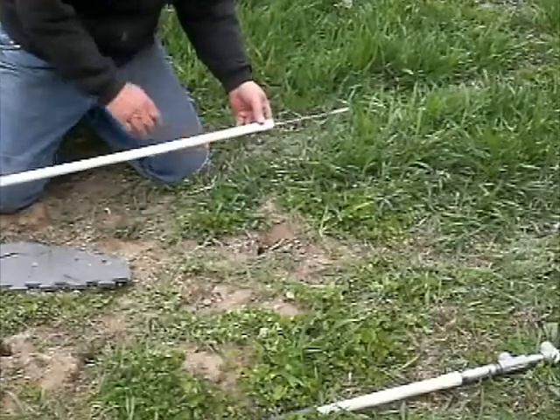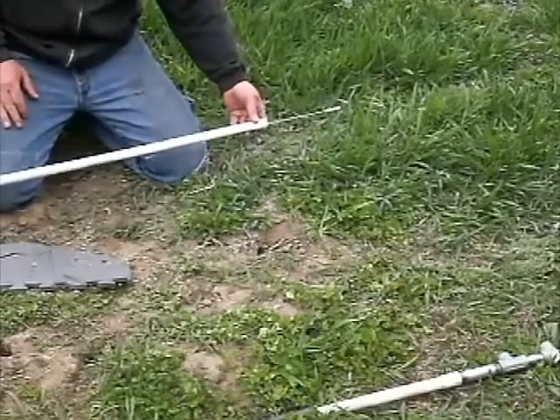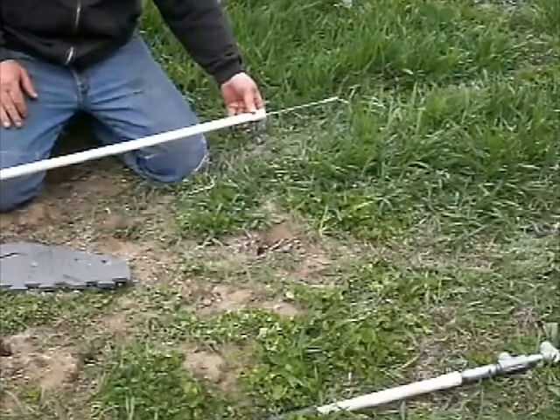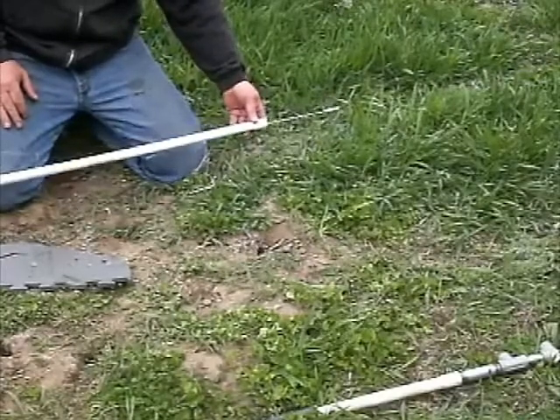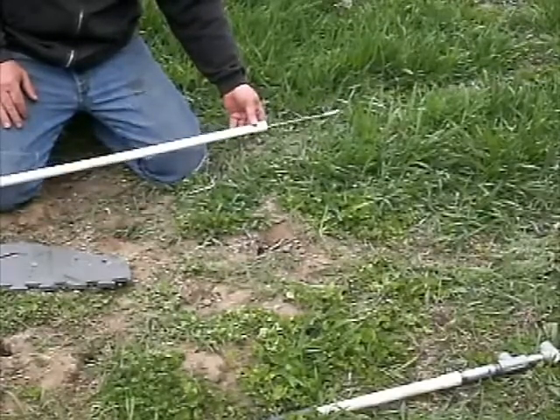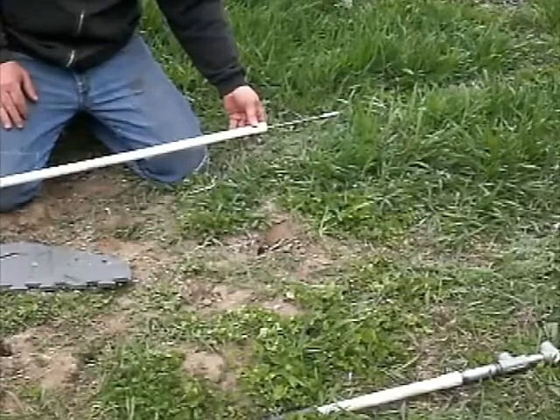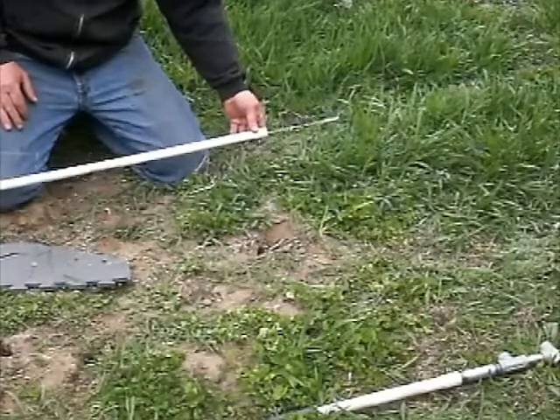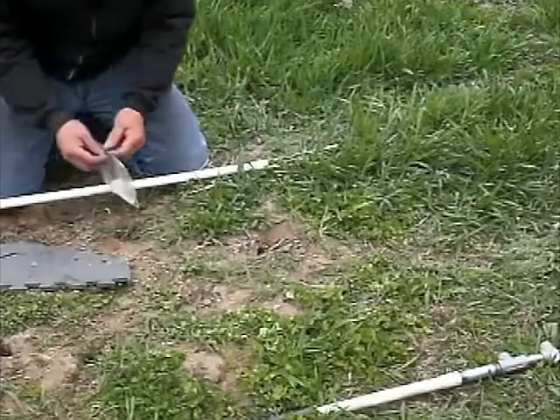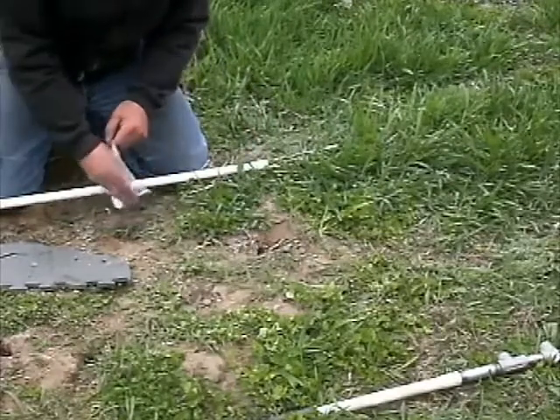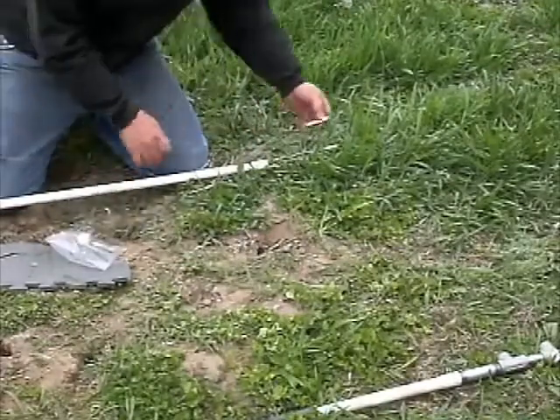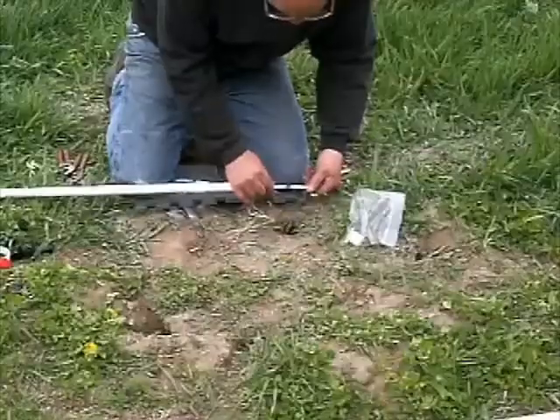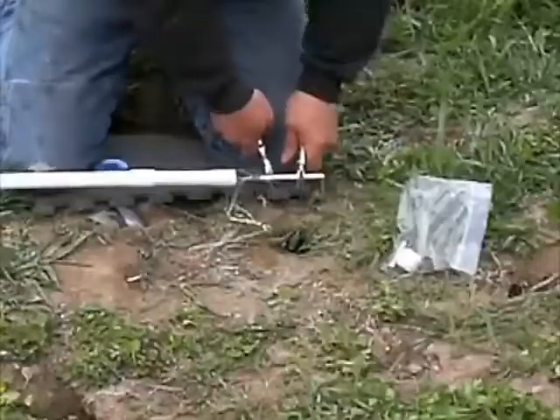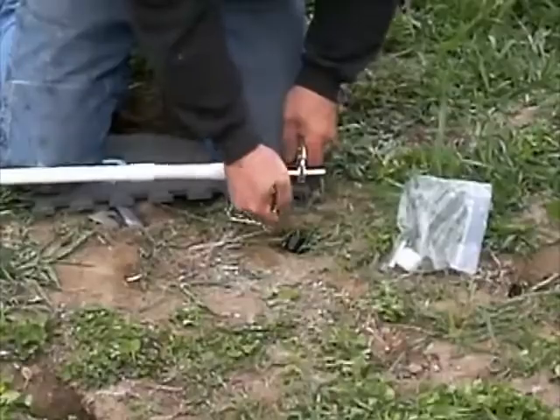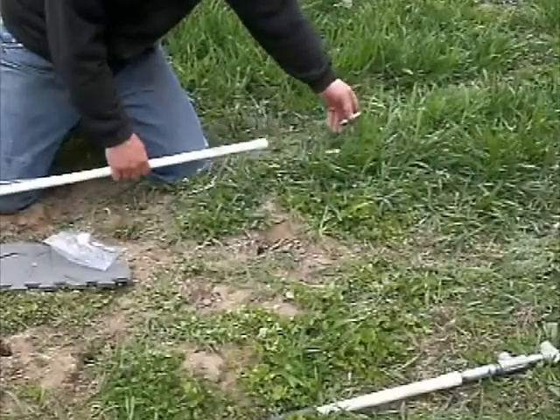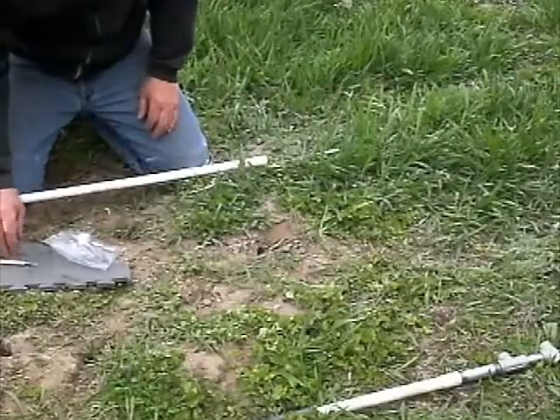If at least 4 inches of the wire rod are not extending past the top of the PVC, make sure that you've pulled the wire rod up until it's stopped, as stated earlier. If you've confirmed that the rod is topped out and you still don't have the wire rod extending at least 4 inches past the top, then you will need to attach the aluminum extension pieces to get the length you need. These are shipped in a small bag. The end goal is to have a minimum of 4 inches and a maximum of 8 inches of rod exposed when you are done with this step.